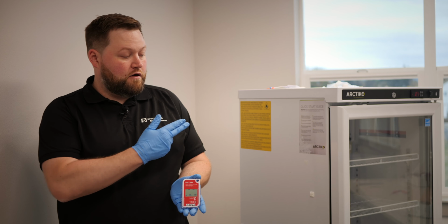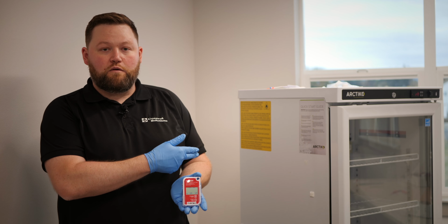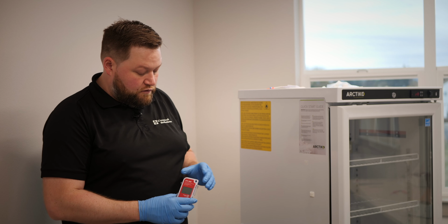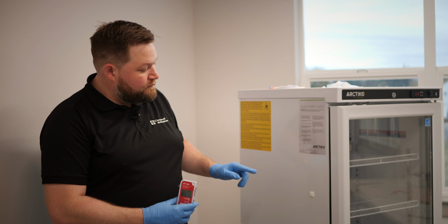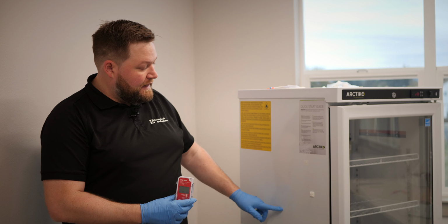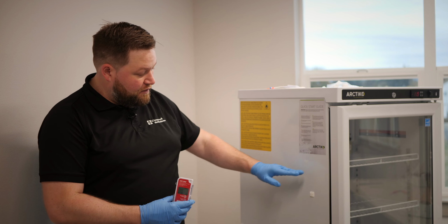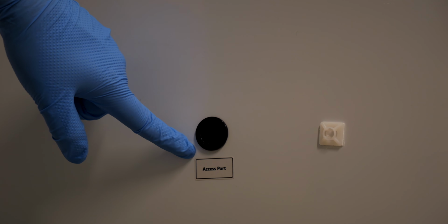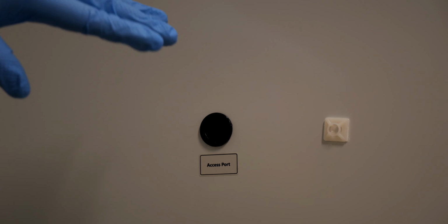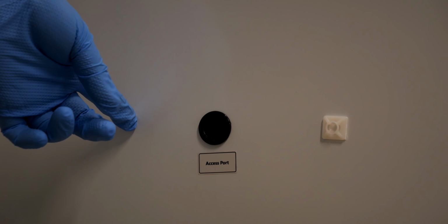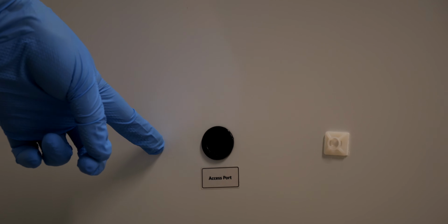Now that we have installed our buffer bottle into our refrigerator, we can continue installing the rest of the LogTag external probe temperature recorder. I'm going to begin the installation by locating my wall mount bracket, inserting my LogTag into the bracket, and I've applied the included adhesive. So now I'm going to install my thermometer onto my vaccine fridge or freezer in a location that's visible to me or my staff, but also within a good distance of the probe pass-through port that allows us to pass our probe from the outside of the unit into the inside where we put our probe buffer bottle.